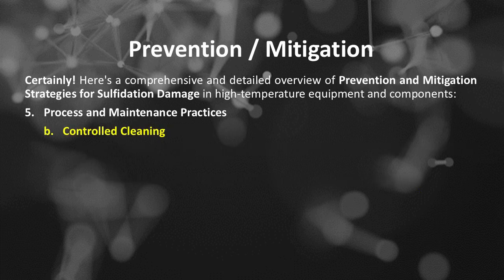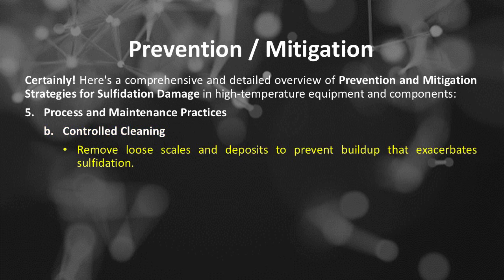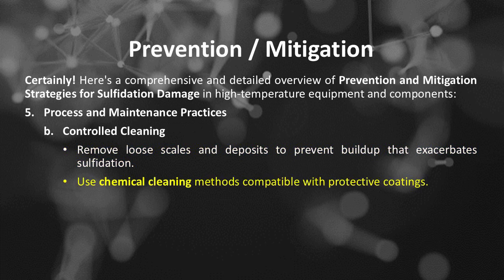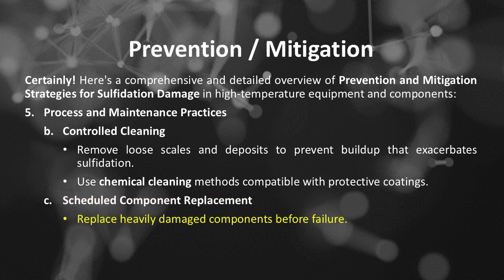Number B, controlled cleaning. Remove loose scales and deposits to prevent buildup that exacerbates sulfidation. Use chemical cleaning methods compatible with protective coatings. Number C, scheduled component replacement. Replace heavily damaged components before failure. Use wear and corrosion allowances in component design.